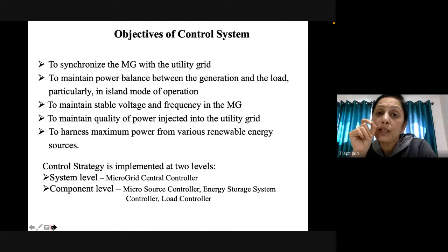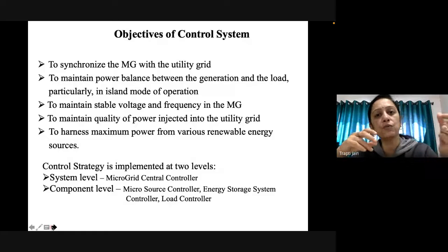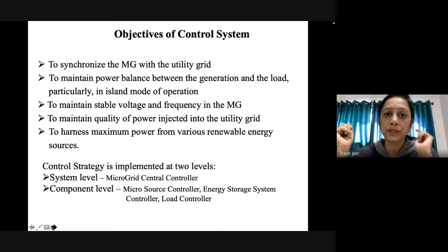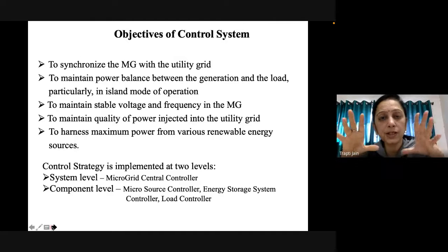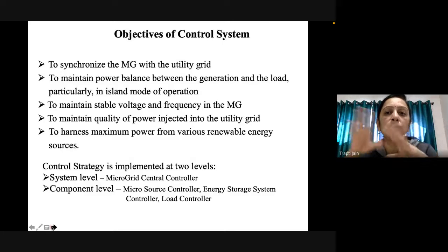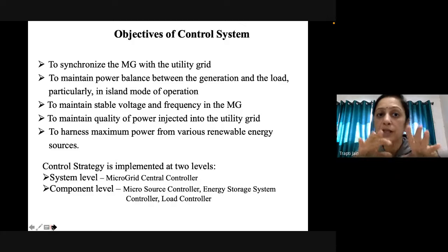When it needs to be resynchronized, it means you need to follow the frequency and voltage of the utility grid. So you need to control all the DGs in a properly coordinated way, so that you are able to track the frequency and voltage of the utility grid. At that time, all these DGs need to cooperate to adjust their power output and voltage to track those of the utility grid.